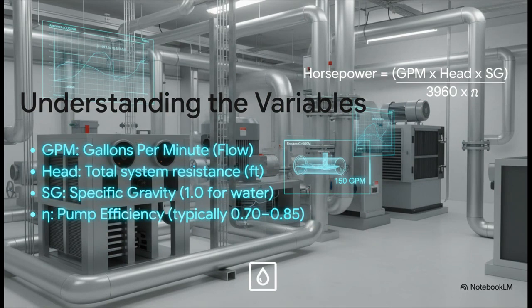We've got our GPM and head. We just figured those out. The specific gravity for water is just 1.0, so that's easy. The last piece is eta. That's the Greek letter for the pump's efficiency. You see, no pump is 100% perfect. Some energy always gets lost. So this efficiency value, usually somewhere between 70 and 85%, just accounts for that real-world energy loss.